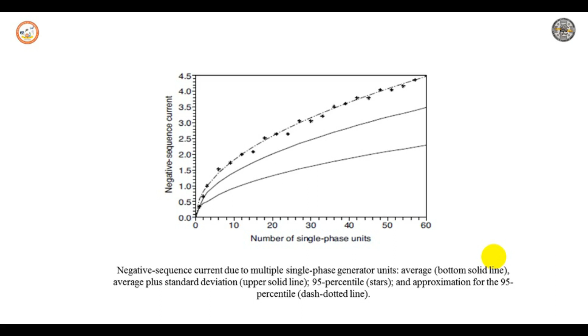With an increase in the number of single phase generator units, the negative sequence current increases. Note that the current unbalance decreases with increasing number of units. What matters to the grid is the absolute value of negative sequence current, as this determines the negative sequence voltage. Using the above mentioned Monte Carlo simulation, the probability distribution function of negative sequence current has been calculated. From this distribution, the average value, the standard deviation, and the 95 percentile are obtained.